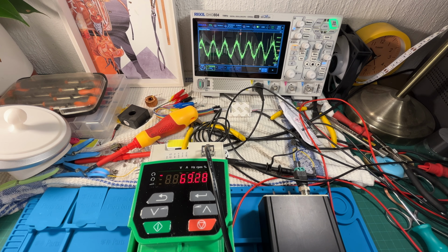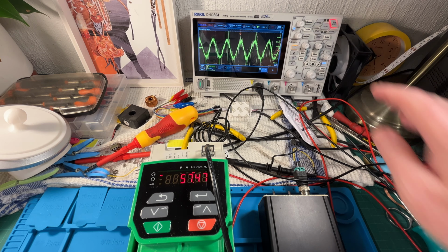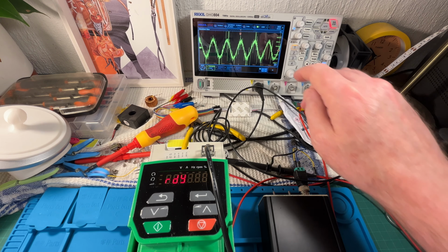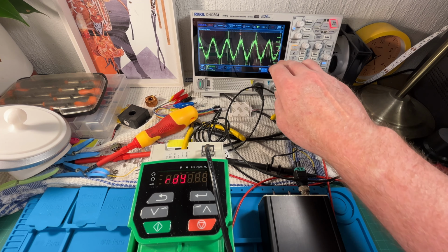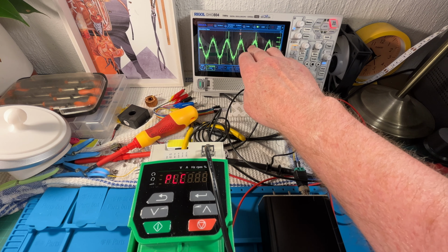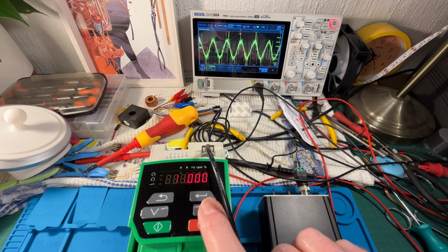Stop our motor. So what's happening here is that the speed increases but your torque decreases, so therefore you've got constant power coming out.